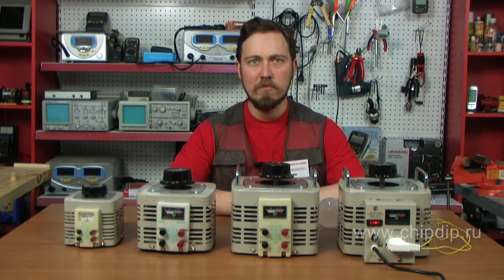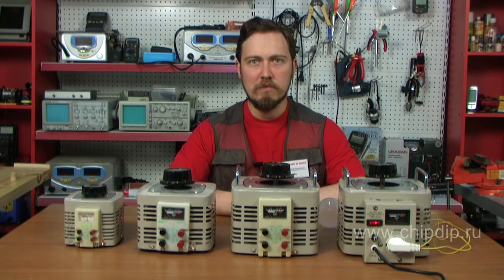The TDGC2 is a single phase autotransformer with smooth voltage control and frequency of 50-60 Hz, ranging from zero to 250 volts at 220 volts under load without breaking the circuit. Rated load currents range from 2 to 80 amperes.